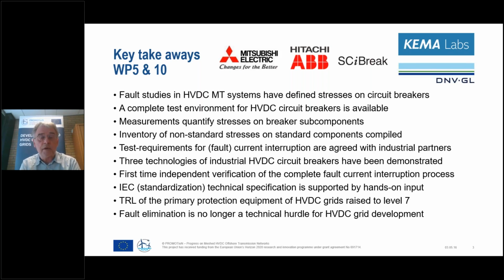HVDC circuit breakers are complicated devices. A lot of standard components, like vacuum circuit breakers, power electronic devices, and surge arresters, are used in a non-standard way. They get non-standard stresses, so they deserve attention from a testing and standardization point of view. Based on that, we defined a test program to which each of the 3 partner circuit breakers were subjected, creating a common platform and a level playing field for each circuit breaker involved in this project. Then, of course, the main part was the actual demonstration of the circuit breakers in the lab.